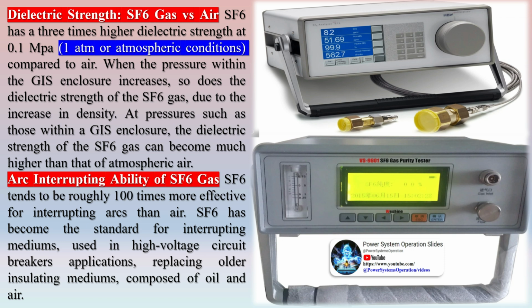SF6 has a 3 times higher dielectric strength at 0.1 MPa/1 atm, or atmospheric conditions, compared to air. When the pressure within the GIS enclosure increases, so does the dielectric strength of the SF6 gas, due to the increase in density. At pressures such as those within a GIS enclosure, the dielectric strength of the SF6 gas can become much higher than that of atmospheric air. SF6 tends to be roughly 100 times more effective for interrupting arcs than air.